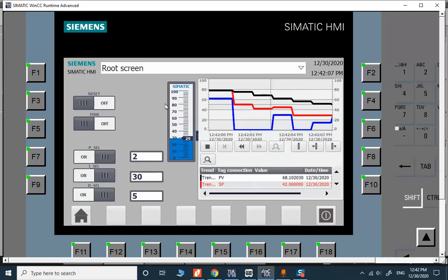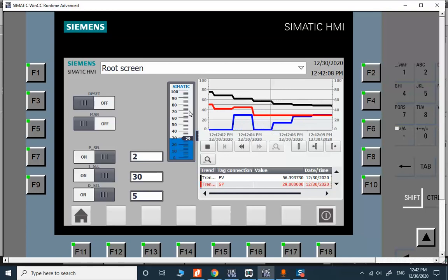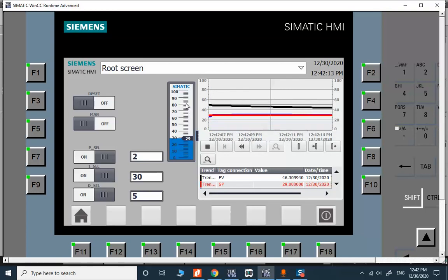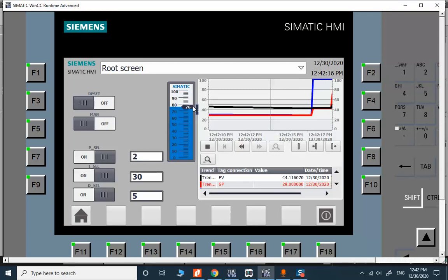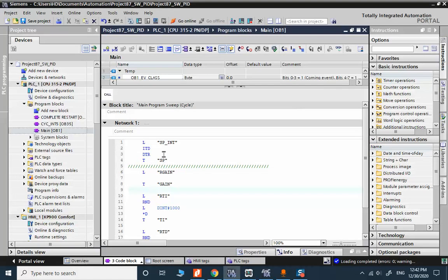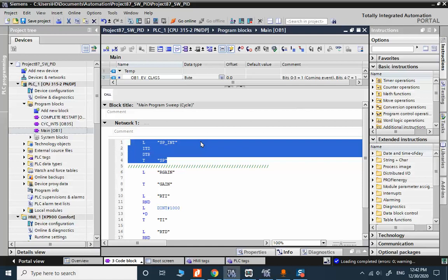The other point is that I just change the setpoint from this slider. I feed the integer variable and then I change the slider. I'm receiving an integer variable in the PLC and simply I need to change that to floating point and feed it to the PID block.